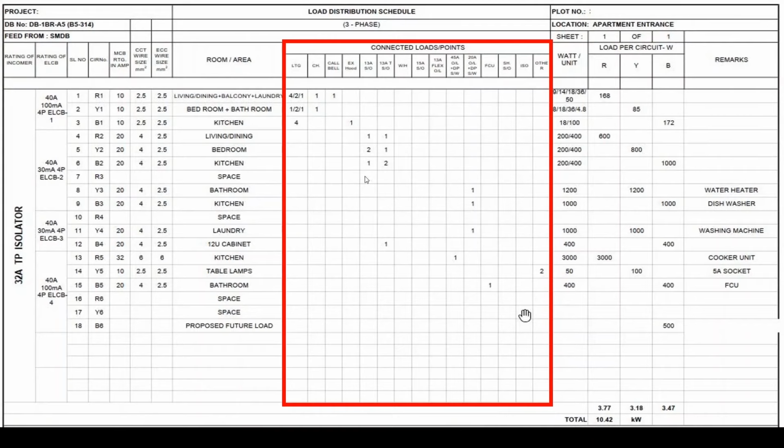So we go on to another example in the power section. This is 1 and 1. If you see here, this is a 13 amp socket outlet, single, and this is a twin. A twin socket is basically two single sockets, so it's an equivalent of two single sockets. So I would put 200 watts for the single socket. This is as per the DEWA standard. And for a twin socket, since it represents two sockets, I would put 400 watts.